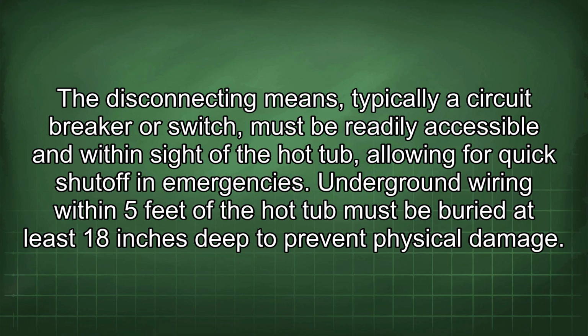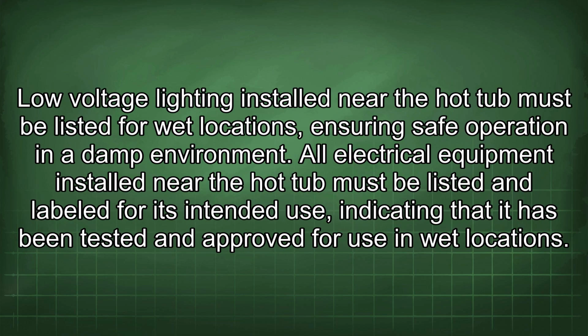Underground wiring within 5 feet of the hot tub must be buried at least 18 inches deep to prevent physical damage. Low voltage lighting installed near the hot tub must be listed for wet locations, ensuring safe operation in a damp environment. All electrical equipment installed near the hot tub must be listed and labeled for its intended use, indicating that it has been tested and approved for use in wet locations.